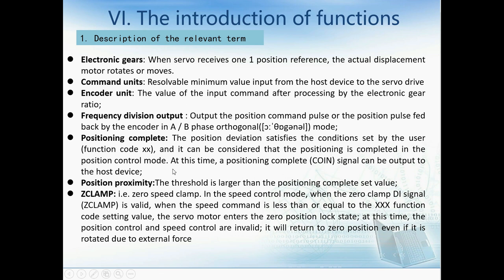Position proximity has a threshold larger than the positioning complete set value. In speed control mode, when the zero-clamp digital input signal is valid and the speed command is less than or equal to the function code setting value, the servo motor enters the zero-position lock state. At this time, position control and speed control are invalid, and it will return to zero-position even if rotated due to external force.